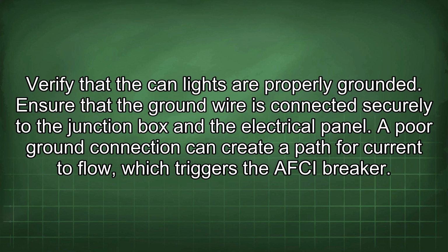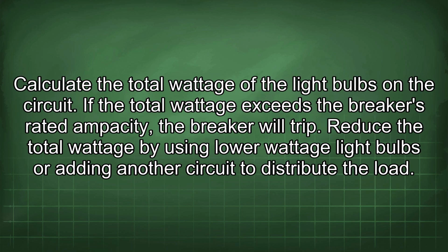Verify that the can lights are properly grounded. Ensure that the ground wire is connected securely to the junction box and the electrical panel. A poor ground connection can create a path for current to flow, which triggers the AFCI breaker. Calculate the total wattage of the light bulbs on the circuit. If the total wattage exceeds the breaker's rated ampacity, the breaker will trip. Reduce the total wattage by using lower wattage light bulbs or adding another circuit to distribute the load.